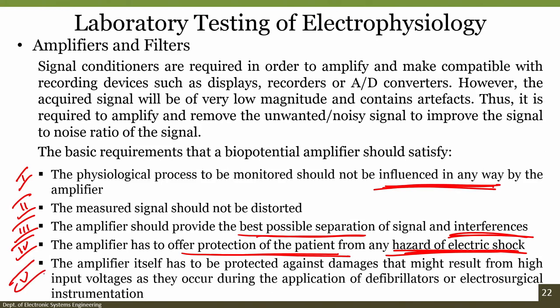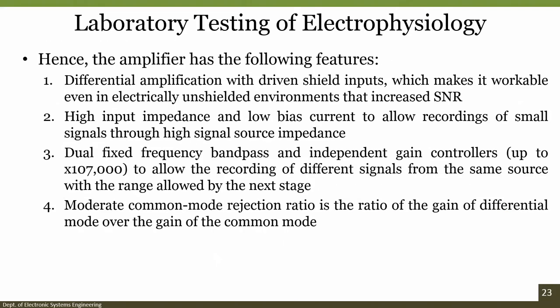Finally, the fifth point: the amplifier itself has to be protected against damage that might result from high input voltages, as they occur during the application of defibrillators or electrosurgical instruments. The electrosurgical instruments as well as defibrillators require high voltage, and this high voltage should not destroy or affect your amplifier. So, the amplifier itself needs to be protected. One is, the amplifier has to offer protection to the patient. Second, the amplifier itself has to be protected.